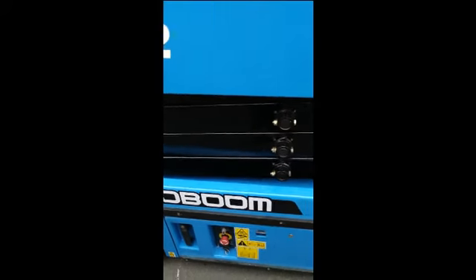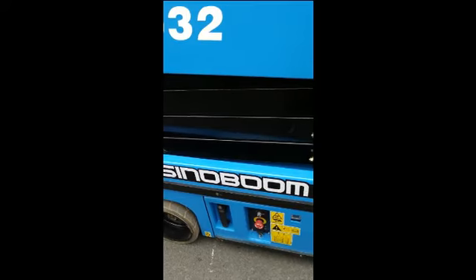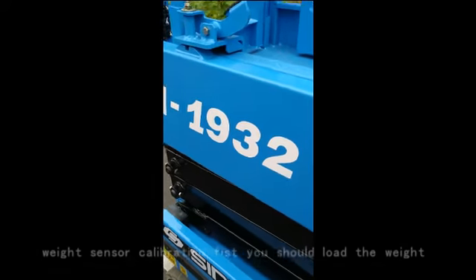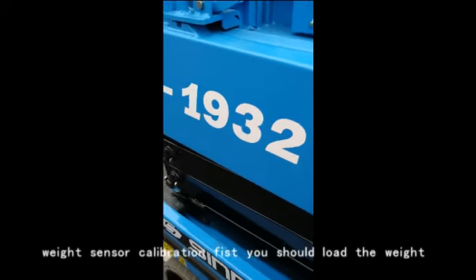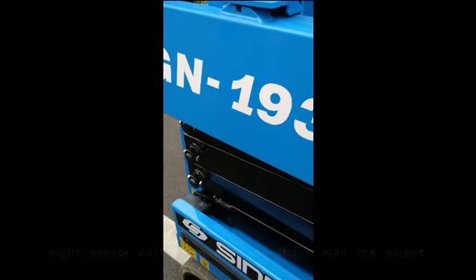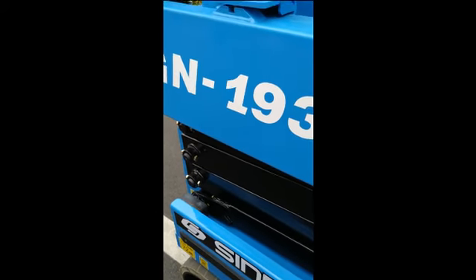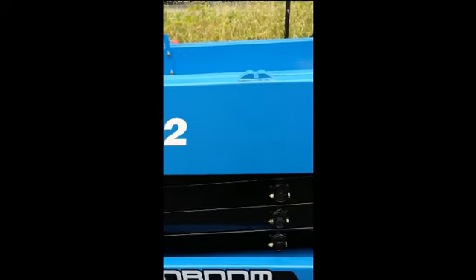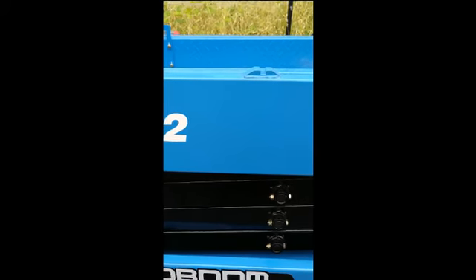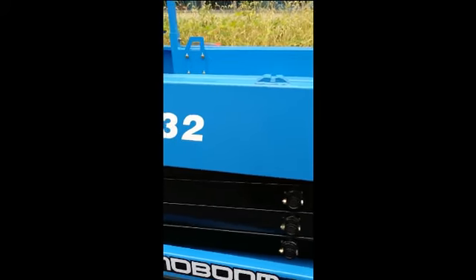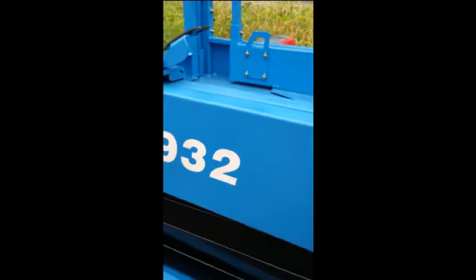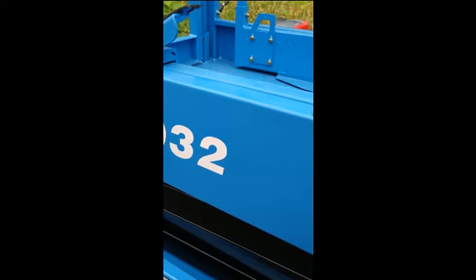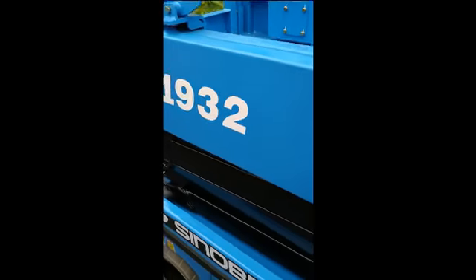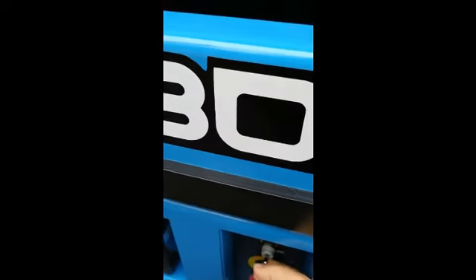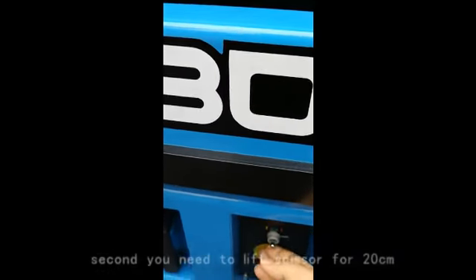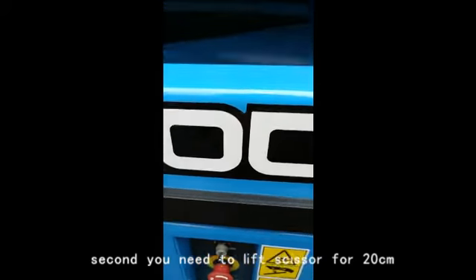For the weight sensor calibration, first you need to load the counterweight, and different machines need different counterweights. For example, if the machine needs 320 capacity, you can load 320 of counterweight. And if your machine capacity is 280 kilograms, you can load about 280. And then you need to raise it about 20 centimeters.